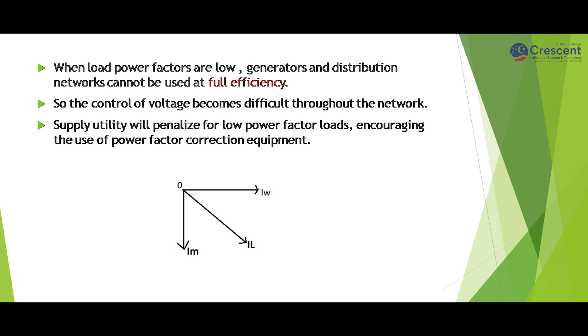When load power factors are low, generators and the distribution network cannot be used at full efficiency, and voltage control becomes difficult throughout the network. Supply tariffs to industrial consumers usually penalize low power factors, increasing the use of power factor correction equipment.